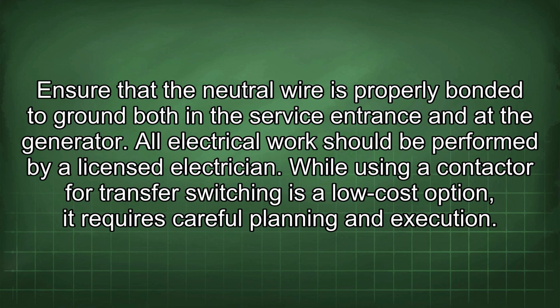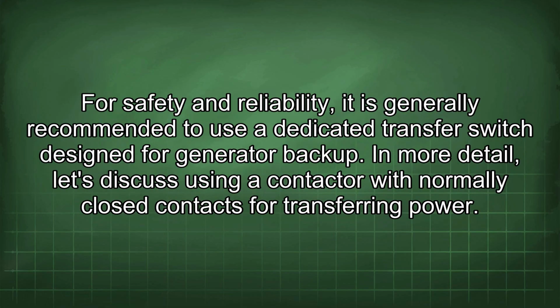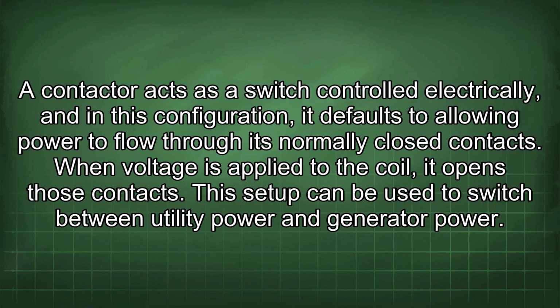While using a contactor for transfer switching is a low-cost option, it requires careful planning and execution. For safety and reliability, it is generally recommended to use a dedicated transfer switch designed for generator backup. In more detail, let's discuss using a contactor with normally closed contacts for transferring power. A contactor acts as a switch controlled electrically, and in this configuration, it defaults to allowing power to flow through its normally closed contacts. When voltage is applied to the coil, it opens those contacts. This setup can be used to switch between utility power and generator power.